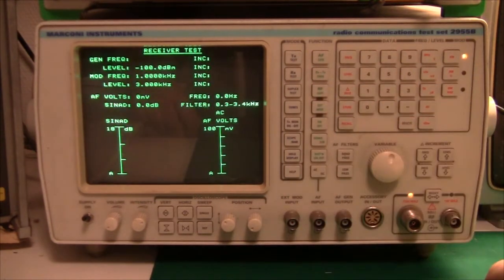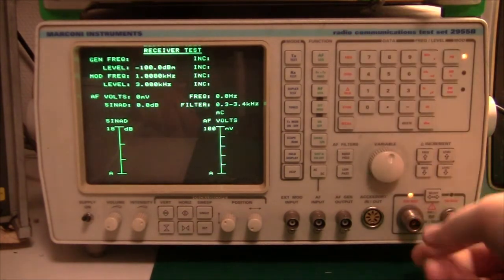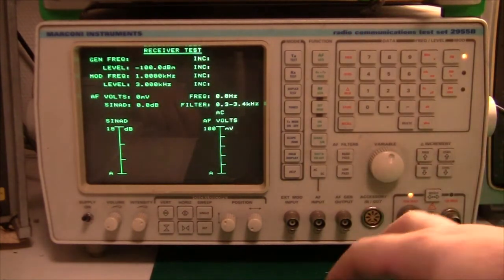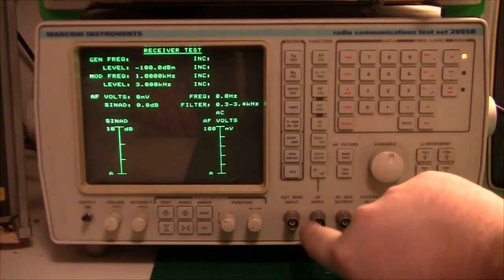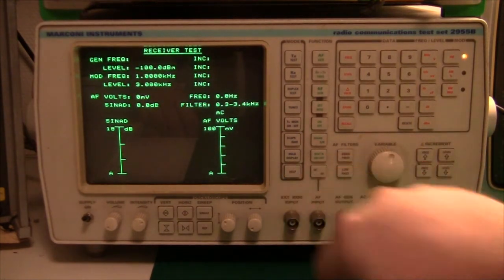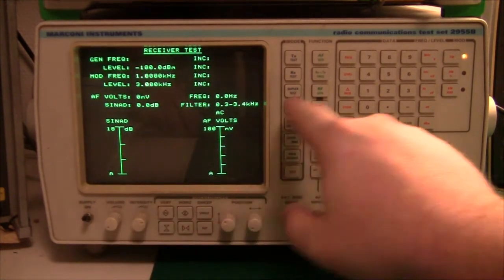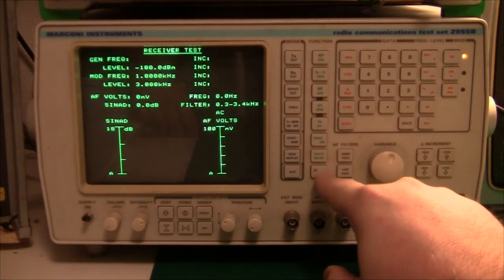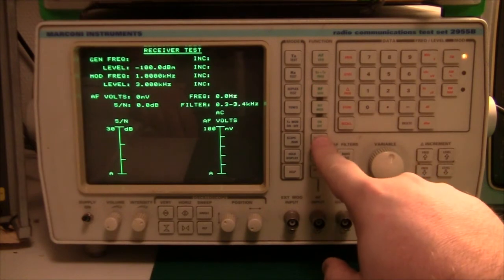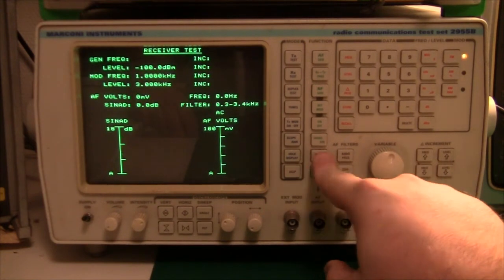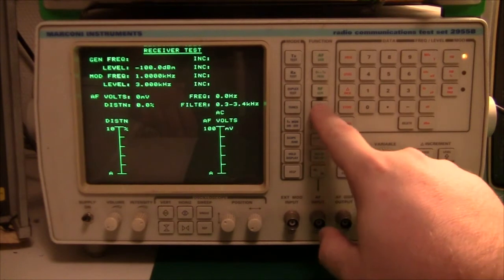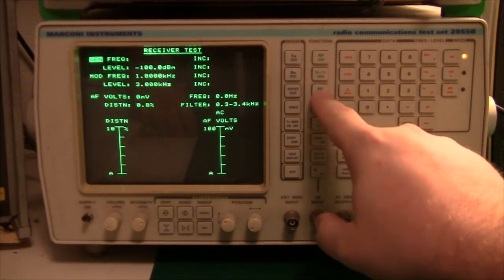We can also test the receiver. And in this mode, we are sending out RF signals from this machine using the same connectors, and then through the radio receiver and back into this connector here. So using this method, we can test stuff like signal noise at different frequencies. We can test SINAD, we can test distortion, we can test different modulation levels.